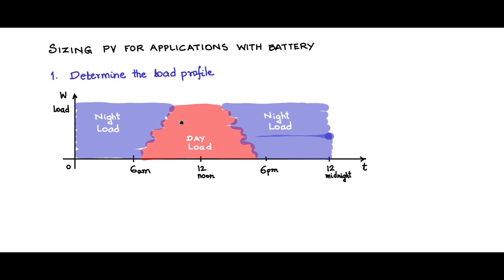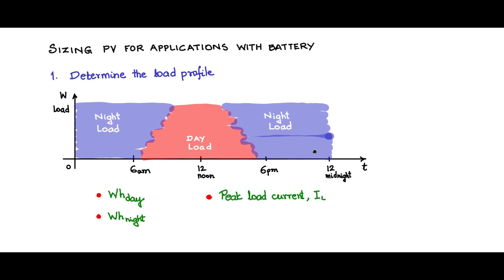After completing the load profile, the key parameters we need are: watt-hours of day load (all loads occurring during the day period), watt-hours of night load (all loads during the night periods combined), the peak load current IL — useful for battery design — and the average load current Il for the entire day, also helpful in designing the battery.